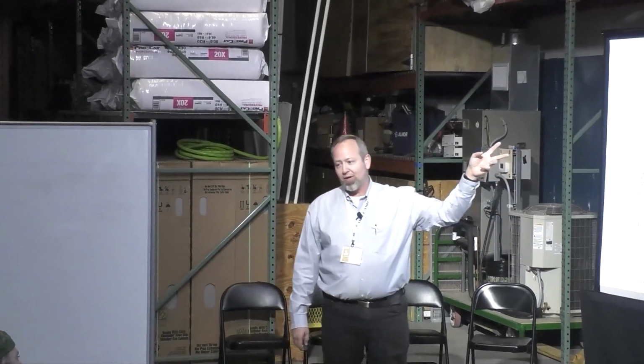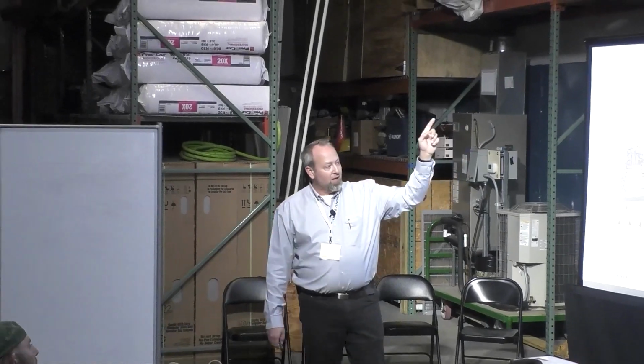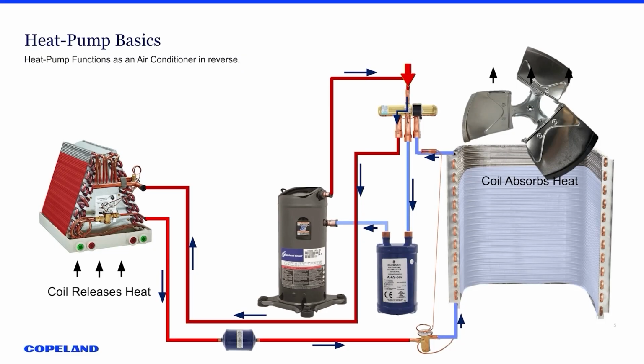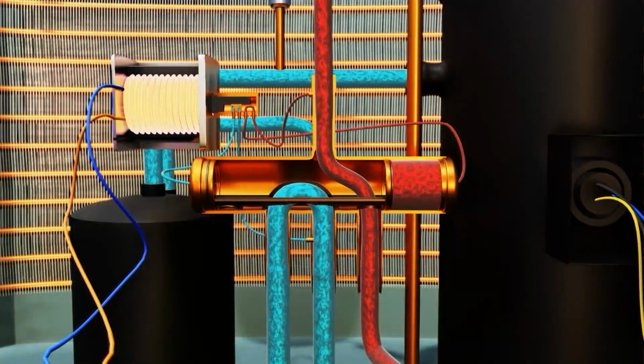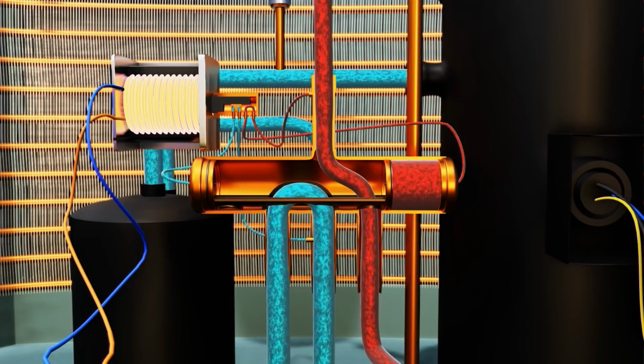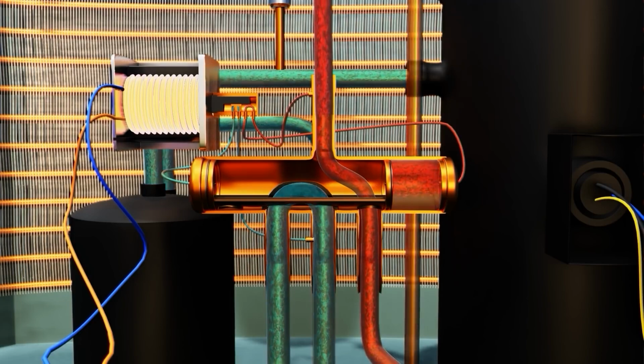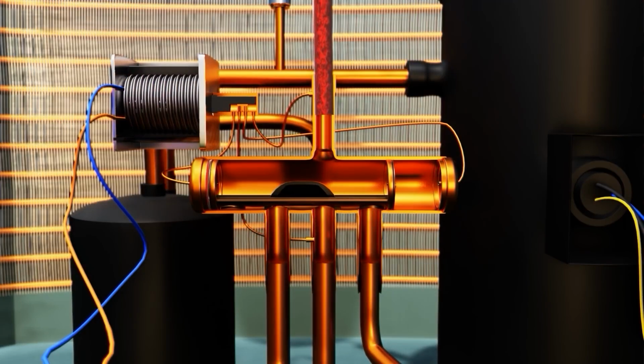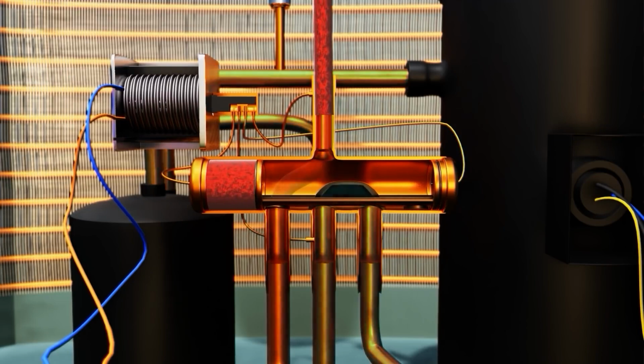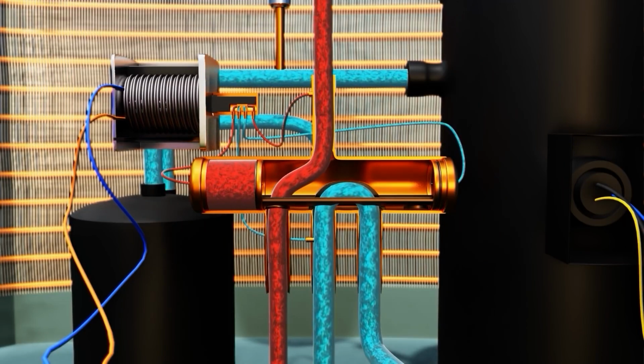Two things to point out with the reversing valve. One, the hot gas always goes in the side of the reversing valve that's a single port, in this case on the top, and the side that's going to the suction of the compressor always comes out the middle of the 3-port side. A simple way to remember as you're looking at heat pumps and working on them: those are 2 ports that are always consistent, and it's just the outside 2 ports that make the difference whether it's heating or cooling.